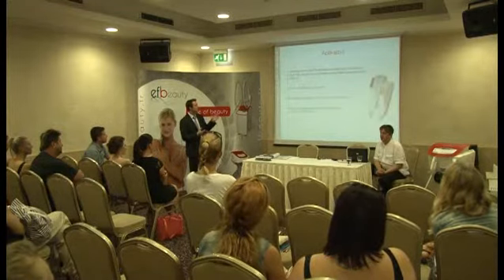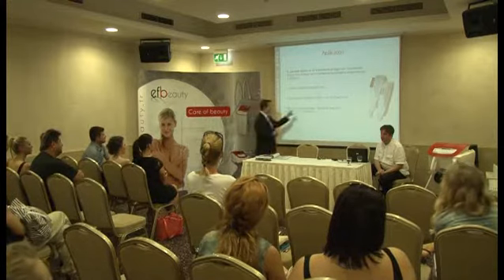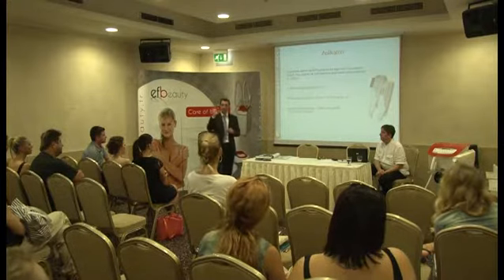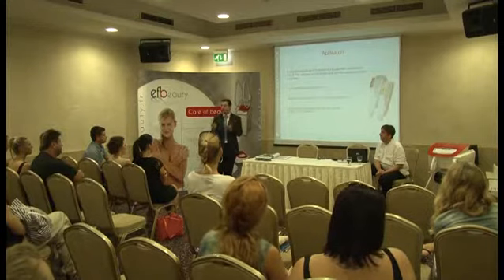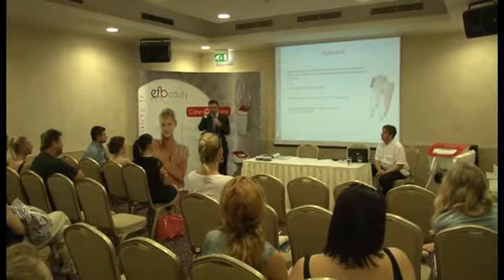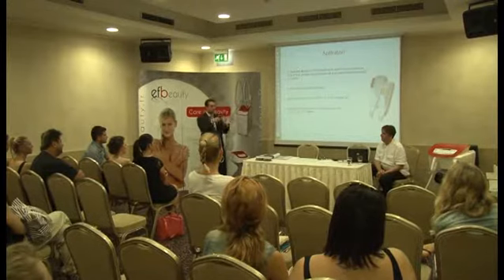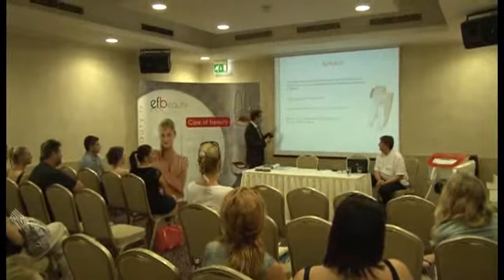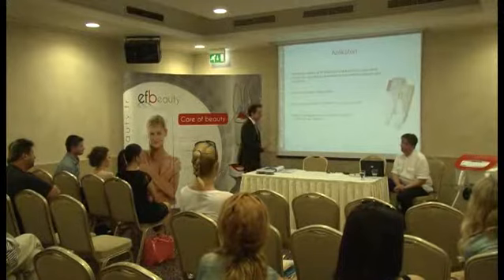Yeah, so now the applicator, what we talked about a little bit earlier. You have two kinds of applicators with the optical depth, which is a little bit different. For hair removal, it's bigger, and for photo rejuvenation, it's smaller. The reason is that with photo rejuvenation, we work more often on the face, and so we need a smaller surface. Than hair removal, sometimes we can have a bigger area. And so you have two kinds of applicators. You have 30,000 flashes and 60,000 flashes.